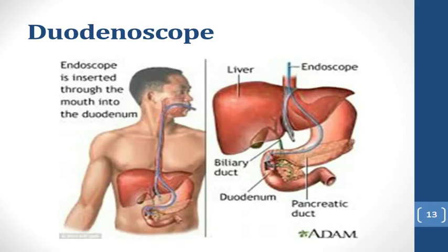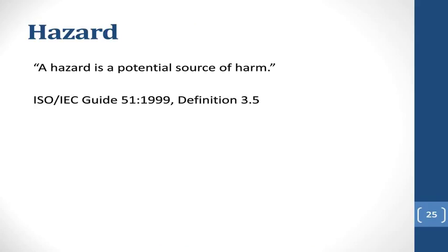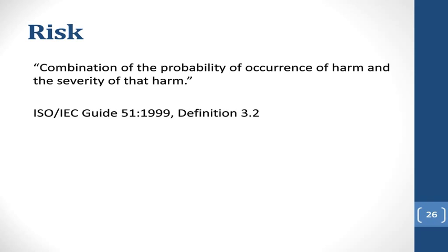So a manufacturer will identify the risks, identify hazards as, well, we have to make sure that the materials used are really flexible and soft and they won't damage any of the soft tissue inside the body. And if you look at any documents for these types of devices, they definitely will have those types of discussions. And what they try to do as a manufacturer is make a risk table.